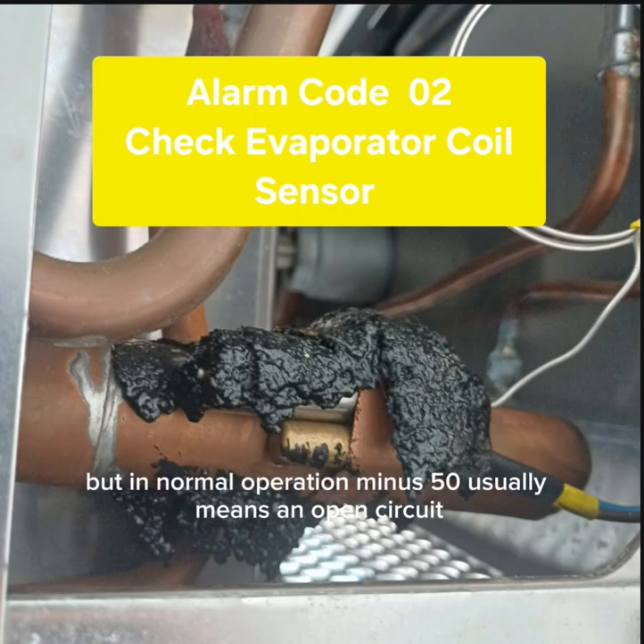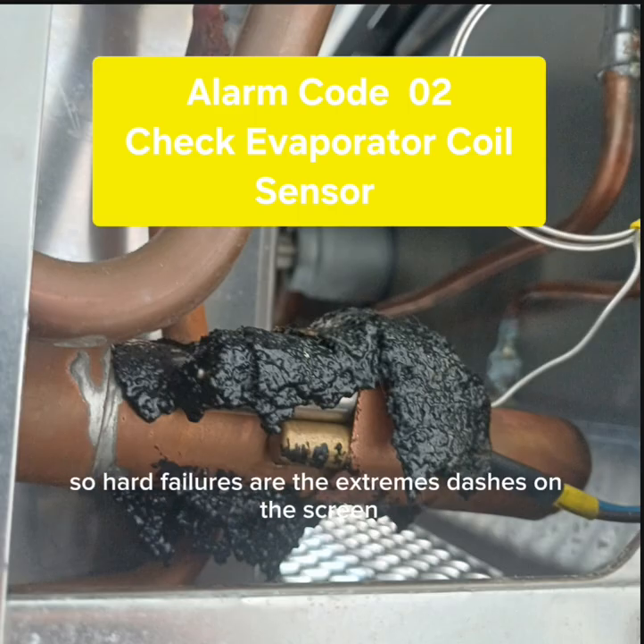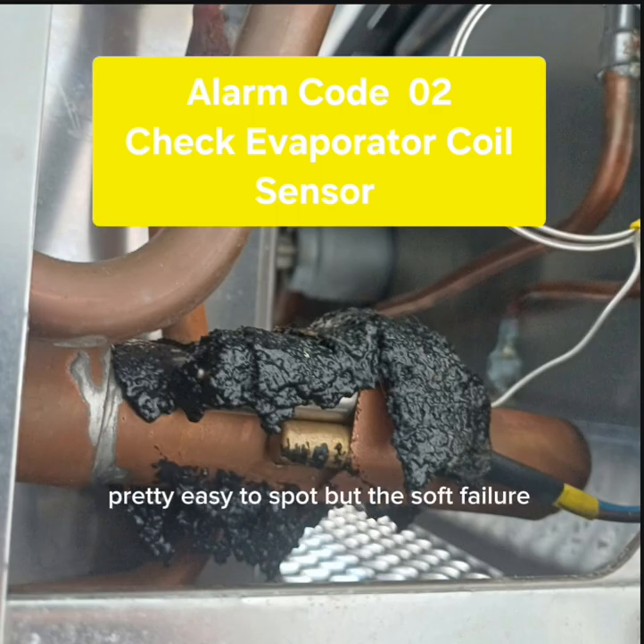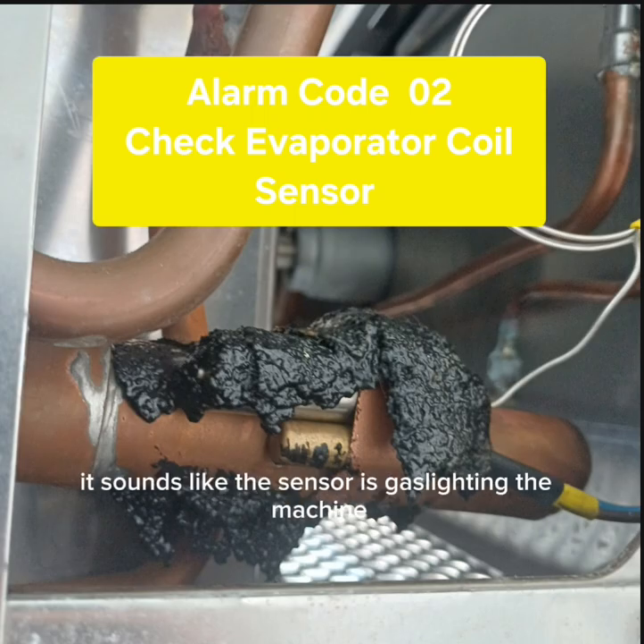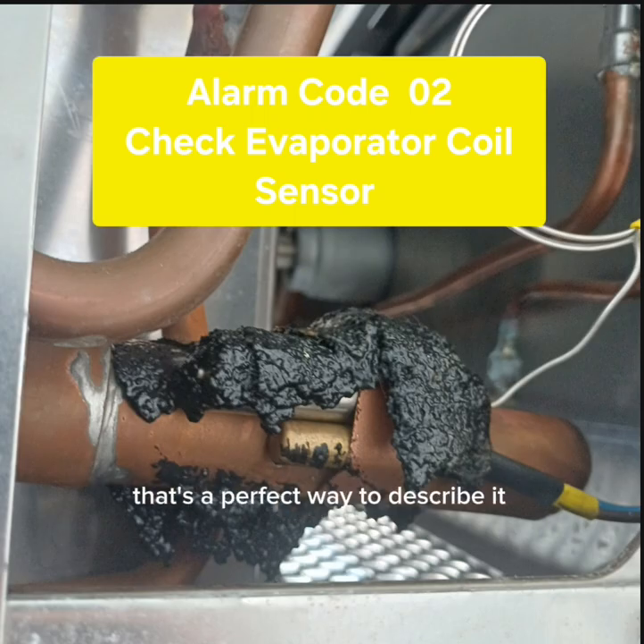But in normal operation, minus 50 usually means an open circuit. So hard failures are the extremes. Dashes on the screen, pretty easy to spot. But the soft failure, that sounds trickier. It sounds like the sensor is gaslighting the machine. That's a perfect way to describe it.